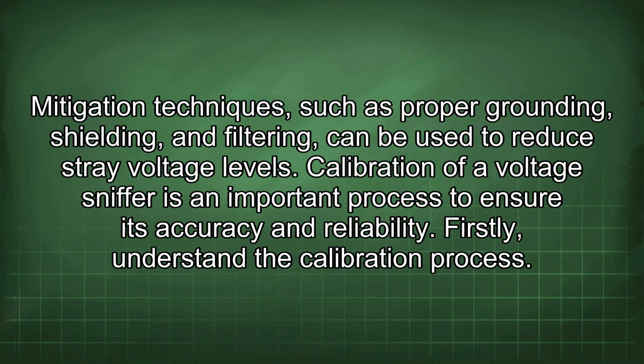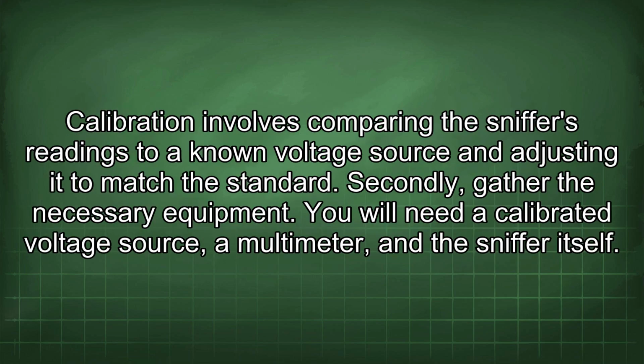Calibration of a voltage sniffer is an important process to ensure its accuracy and reliability. Firstly, understand the calibration process. Calibration involves comparing the sniffer's readings to a known voltage source and adjusting it to match the standard. Secondly, gather the necessary equipment. You will need a calibrated voltage source, a multimeter, and the sniffer itself.